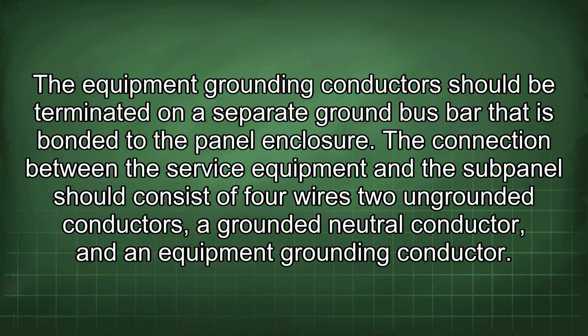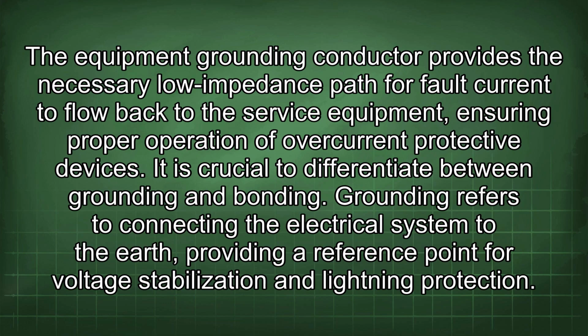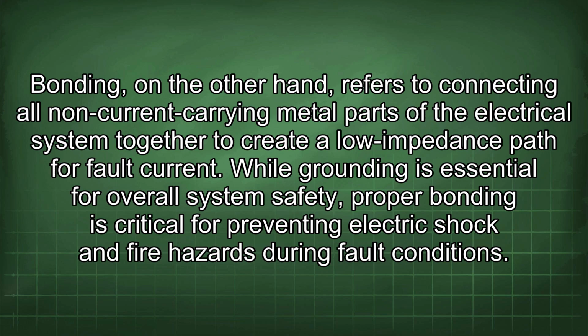The connection between the service equipment and the subpanel should consist of 4 wires: 2 ungrounded conductors, a grounded neutral conductor, and an equipment grounding conductor. The equipment grounding conductor provides the necessary low-impedance path for fault current to flow back to the service equipment, ensuring proper operation of overcurrent protective devices. It is crucial to differentiate between grounding and bonding. Grounding refers to connecting the electrical system to the earth, providing a reference point for voltage stabilization and lightning protection. Bonding, on the other hand, refers to connecting all non-current carrying metal parts of the electrical system together to create a low-impedance path for fault current.